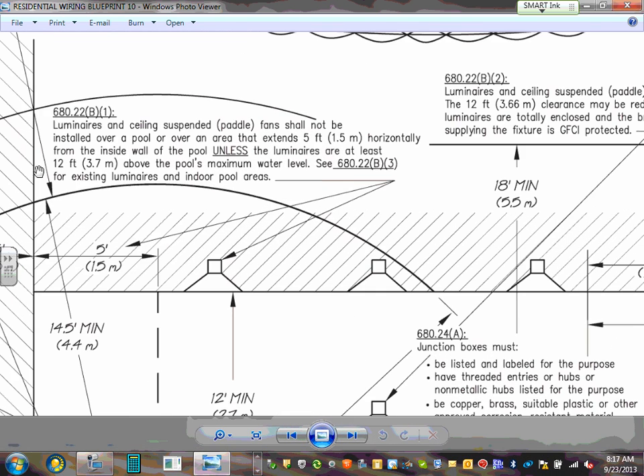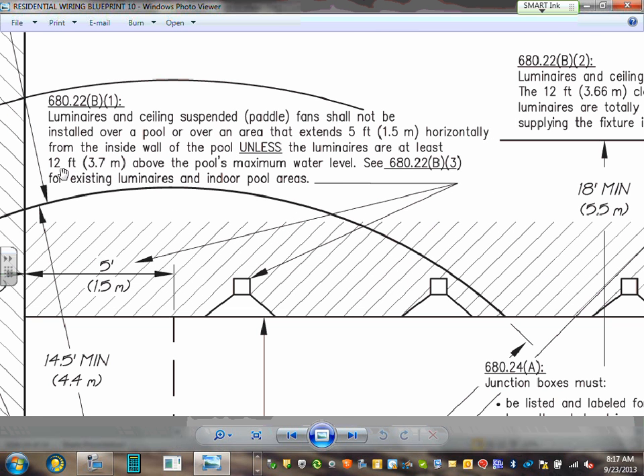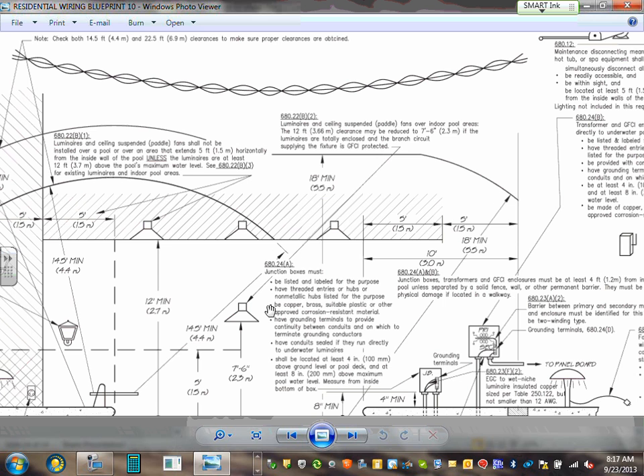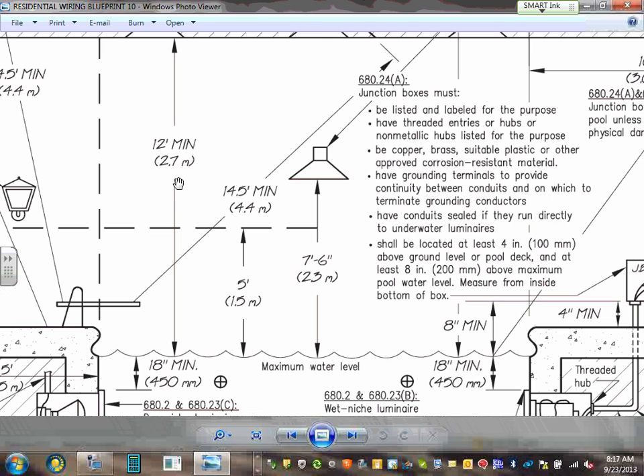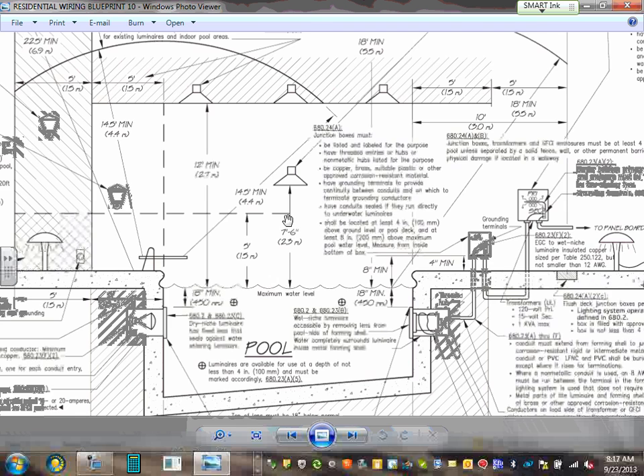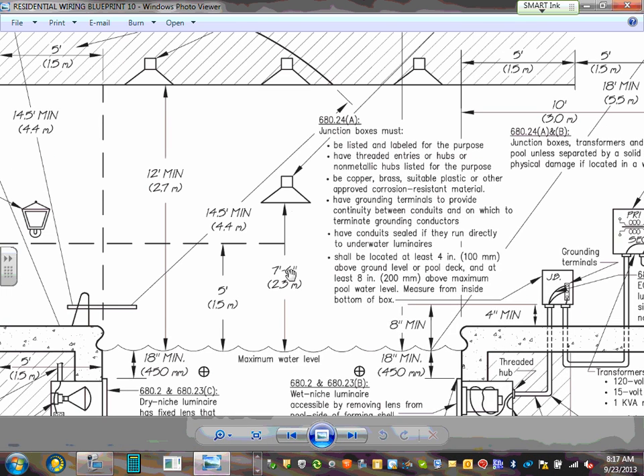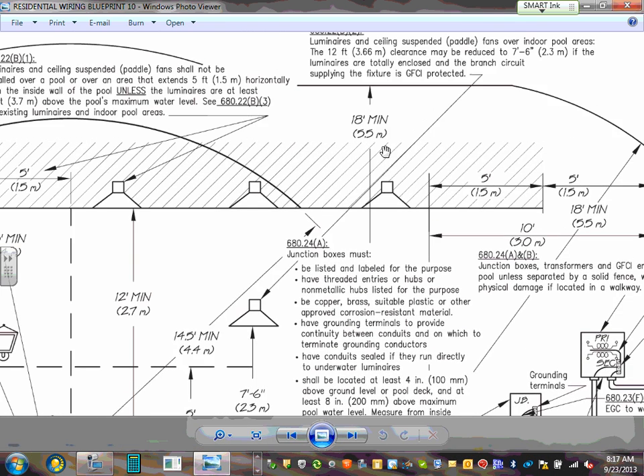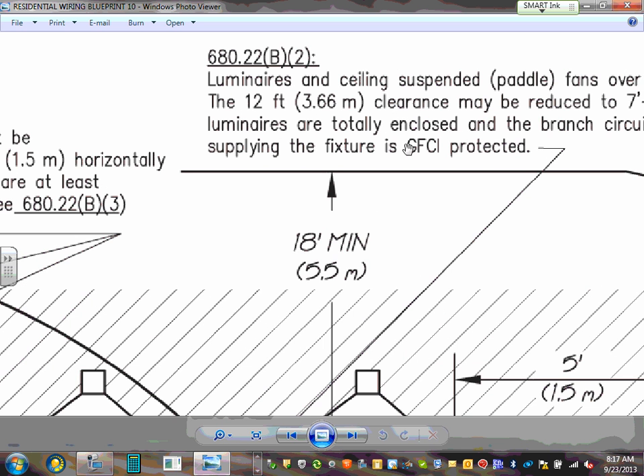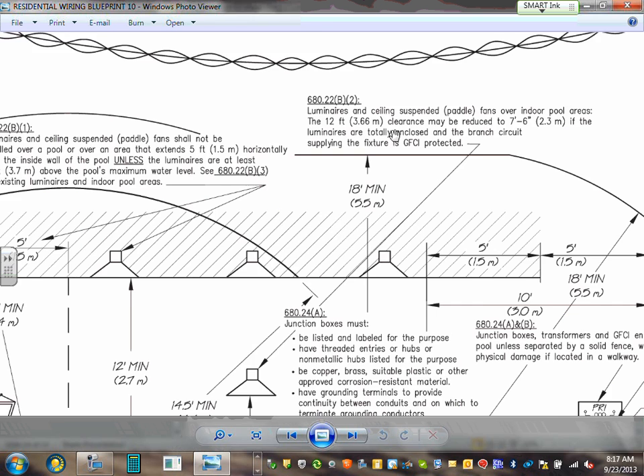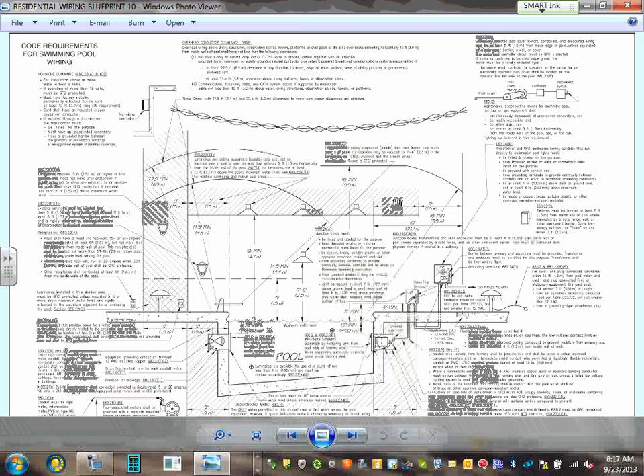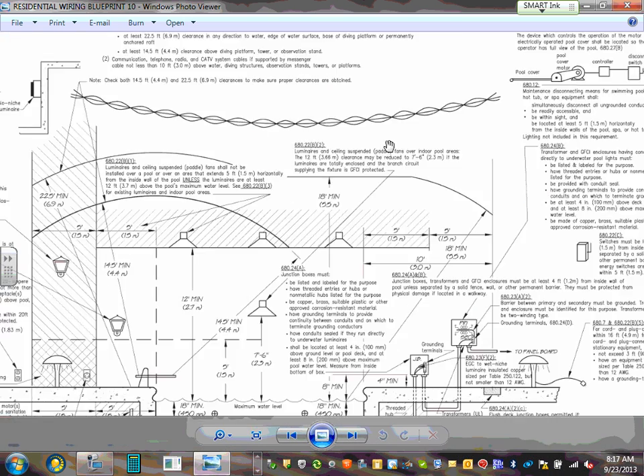The rules for luminaires right above the water: unless the luminaires are listed, they have to be what? 12 feet above the water. Unless they're listed. When you put them right above the water, you have to put them 12 feet above the water unless they're listed. If they're listed, then you can put them as low as, not lower than, 7.5 feet, but that will trigger you to put what? GFCI protection. If they're listed, you put them at 7.5 feet, but you have to put GFCI protection for them. So the rule is what? 12 feet, lower to 7.5 if they're listed, and what do you do? You GFCI them. So that's the rule for that one.